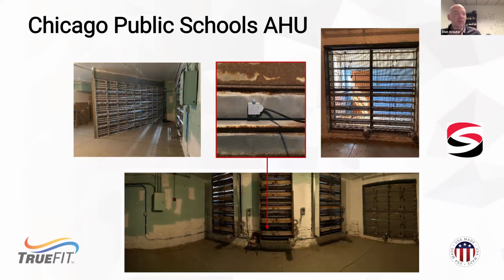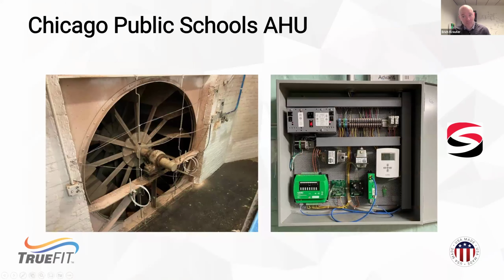And this is standing in that mixed air chamber. So you'll see that if you really look at the bottom, there were 3 outdoor air dampers, each with airflow measurement already installed. This is a pneumatically controlled air handler. So we see the pneumatic dampers or actuators here all ganged together. The return is on the right. This was a dual delivery air handler. So it actually had 2 return dampers, one from the east side of the school, one from the west. And if we look at the fan, this is about an 8.5 foot inlet, about a 12-foot fan, and then half the airflow got split off for, again, each half of the building with independent heating coils.